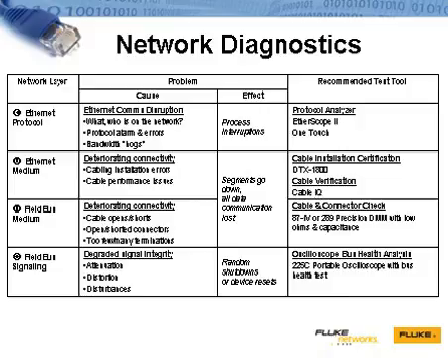Using the diagram, following the flow of control data from left to right, the core elements are the Ethernet communication protocol between the server and the switches, the Ethernet infrastructure over the Cat5e, fiber or wireless, and then down to the FieldBus cabling infrastructure, like twisted pair or standard AWG, and then the FieldBus physical layer electrical signaling. Performing critical measurements to understand if the components meet the specific parameters or characteristics defined by the standard can help diagnose a problem to a specific location or component.